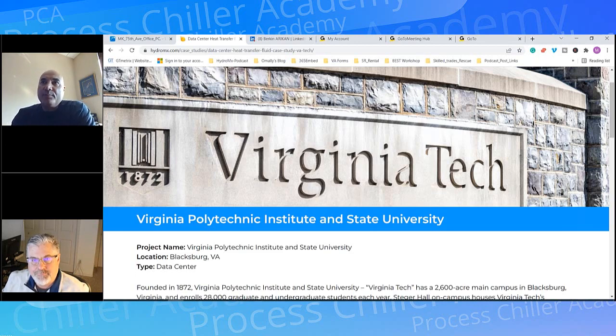With propylene, let's start with propylene. Propylene glycol is a troubled product. Let me take another two steps back. Governments, the decision makers on what's toxic and what's not, what can be used and what cannot, don't really understand this technology. Propylene, yes, it's better than ethylene, no doubt. But once you add inhibitors, which you have to for any propylene solution, it becomes toxic automatically because of the inhibitors. Therefore, in New York now, you have to reclaim even propylene glycol solutions because of the nitrites, the nitrates, the molybdates, the potassium phosphates, what have you. They have to reclaim that now.